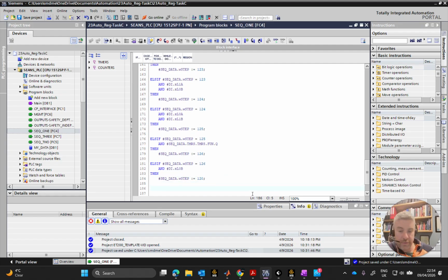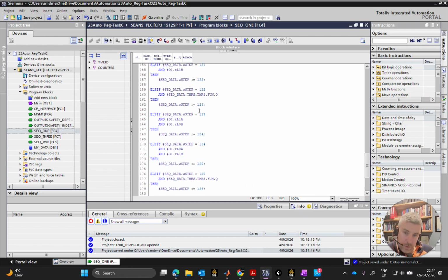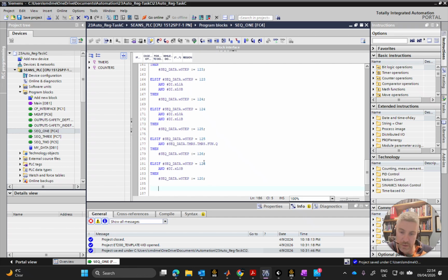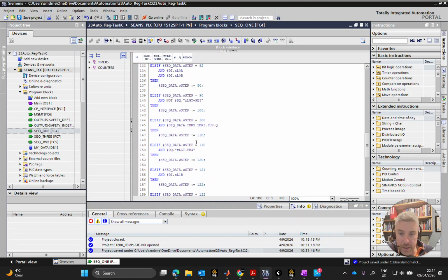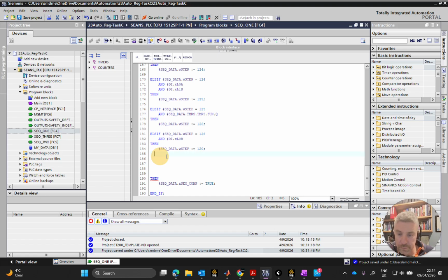So then 120 might fire me on to 121, and I'll have to do all that again. 122, then I go to 123, 123 to 124, 124 to 125, 125 to 126, 126 back to 120. 120 then might fire me on to 130. So I'm on to that light. I want to turn it off, so it's an and not. Right? I'm going to take these ones here, line underneath it. So if I'm equal to 130 and not push button 4, go on ahead there to 140.